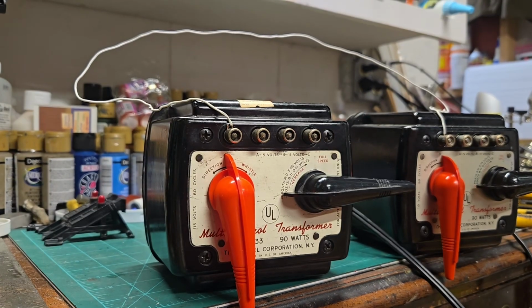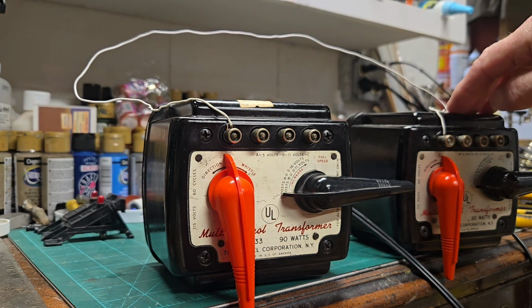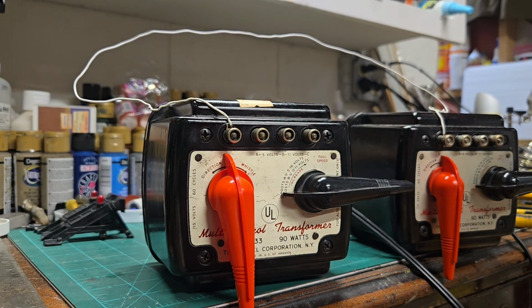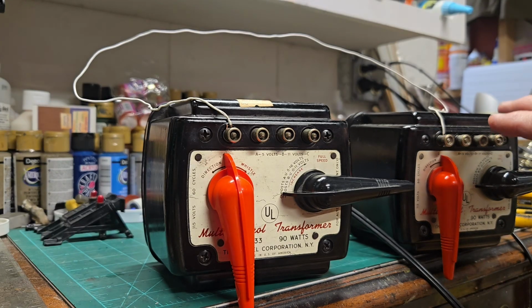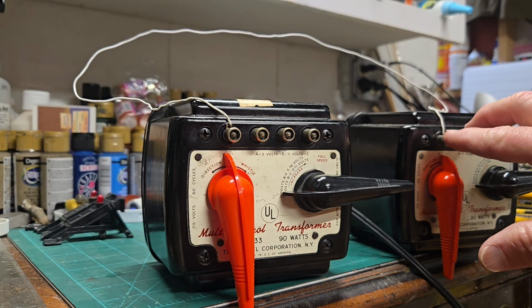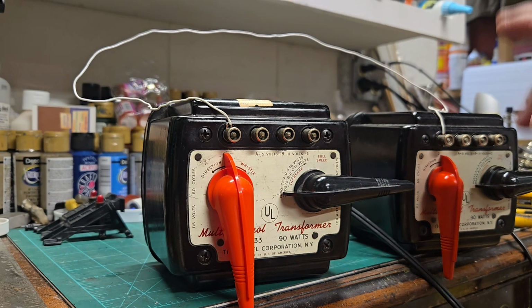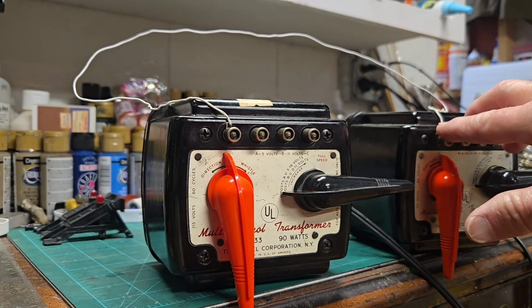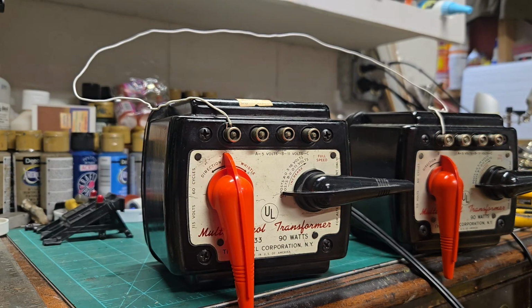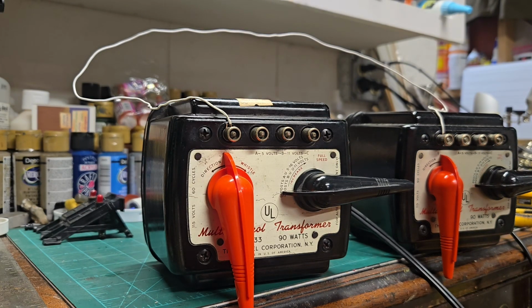I want to clarify something real quick. In the last video I left the impression that the polarity on this transformer cannot be reversed by the wall outlet - you can, it will reverse the polarity. But the issue I had was that this transformer was already phased with my other transformers to work off the variable voltage setting. It wasn't until I tied into this fixed setting that it caused the problem, throwing it out of phase somehow.